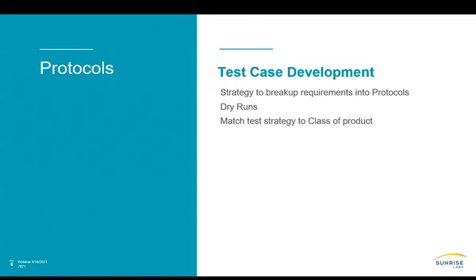justify when you're rerunning. A couple other cautionary tales about protocols I've seen in past lives, where people have, in essence, written a requirement into a test protocol. So I think you want to test the requirements as they're written and as they're given. But the example in this case was working on a software release, and the software was meeting all the requirements, and then someone said, well, it's failing test step 35 or whatever the number is. And I'm like, well, that's not a requirement. And they're like, well, that's the way the field product works, so every product that ships now has to have that same feature. And I'm like, well, that's a requirement, right? So those types of requirements should be fed back into the requirements documents so that you're always in sync with the development team and the QA team.